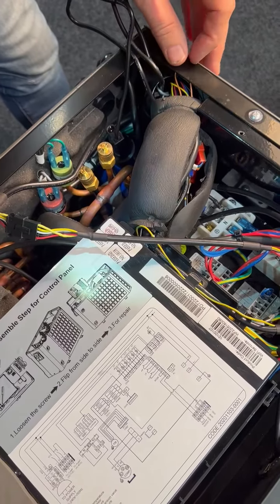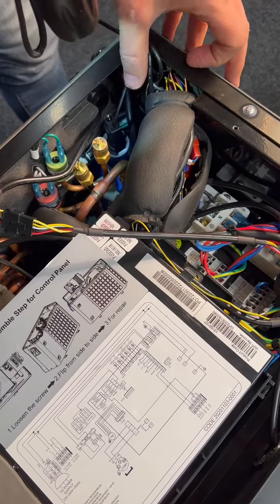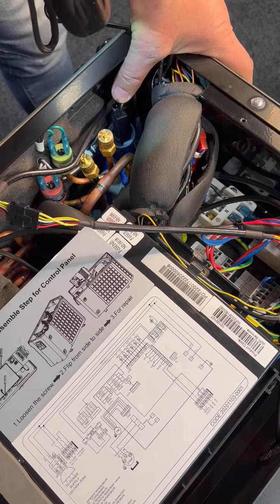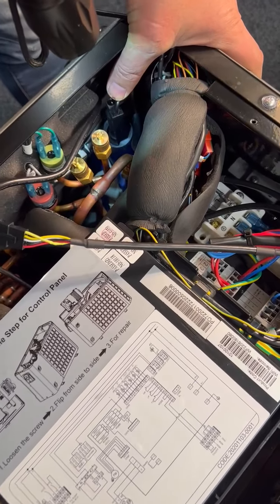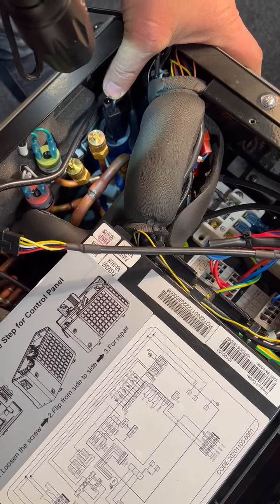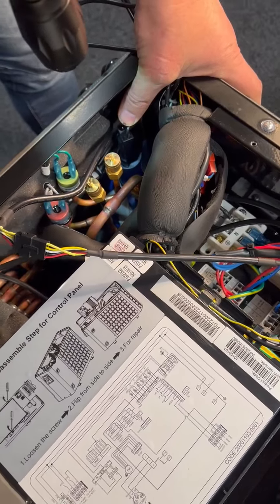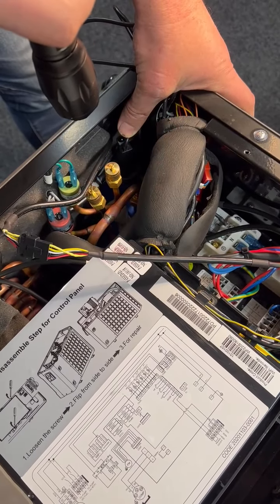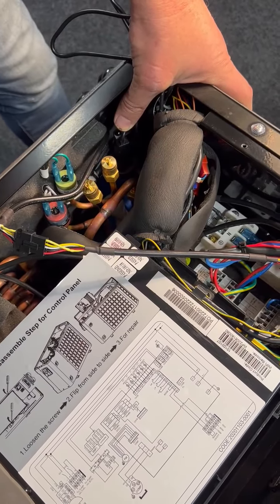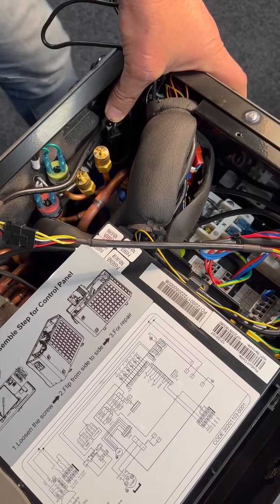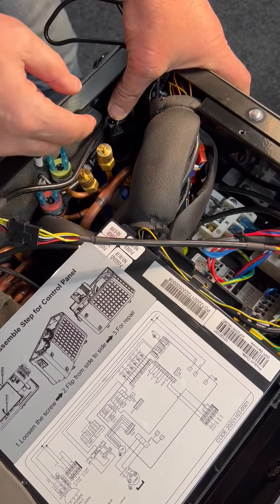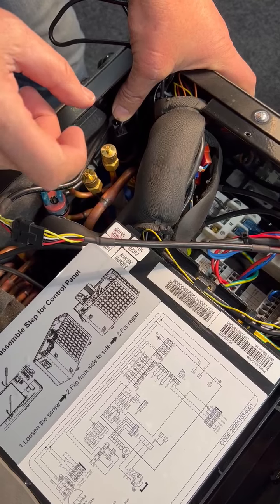We're just going to show you how to change the flow switch. The flow switch is just inside the heat pump, as you can see in there, the little black paddle, and it's got a nut on it, and that's connected to the heat exchanger. And that's where the water flows out of the heat exchanger. So if the heat pump comes up with a flow fault, the most common thing is the paddle is broken or the contact is broken.